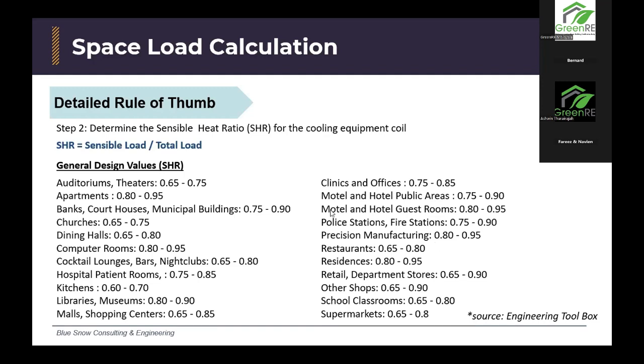So for example, for kitchens and cafeterias, you might notice it to be 0.6, 0.7. Why? Because there's a lot of food. Food is very moist, you've got a lot of moisture there, and you want it removed or you may end up with mold issues. I've actually seen even hotels that did not consider that, people bringing food and eating, especially five-star hotels, big names, with mold issues because they didn't design the system with latent load in mind. Their coil ratio was something more like 0.8, which was meant for office space. Office is around 0.8. So they sized the coil ratio at 0.8 and did not take into account the latent load. But again, this is rule of thumb. This is normally where your ballpark is going to be.